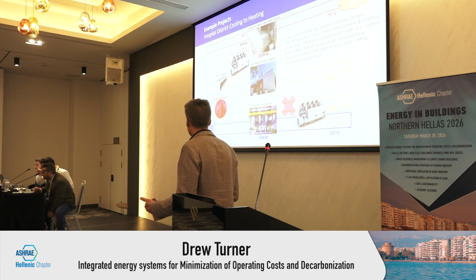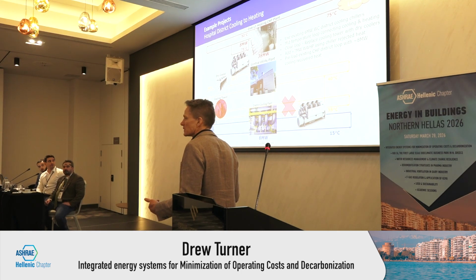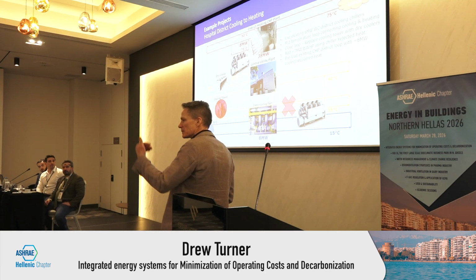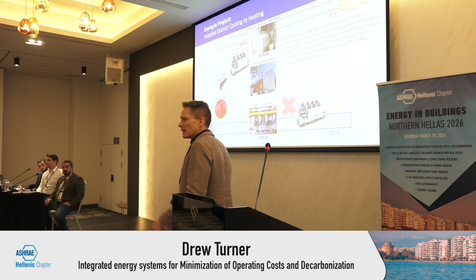In this case we said, okay, close the loop. What we meant is replace that cooling tower with a dry cooler, boost it up a bit more, because this is your base load heating—that 8 megawatts is your base load heating. If you're recovering heat all the time, it doesn't matter if you're recovering it at a higher temperature, because ultimately you boost it up with a second stage to supply the district energy system, the campus energy system.